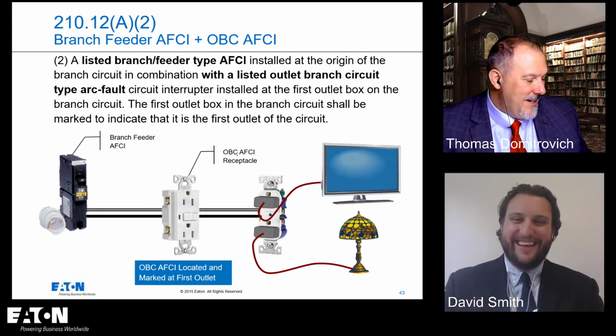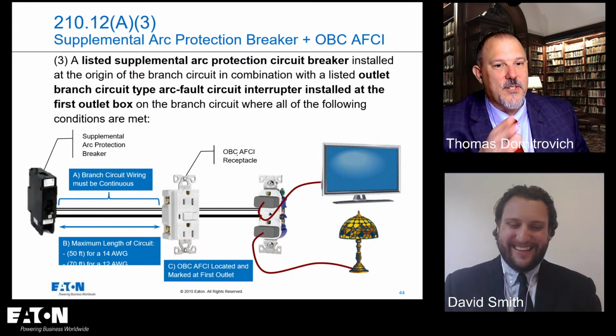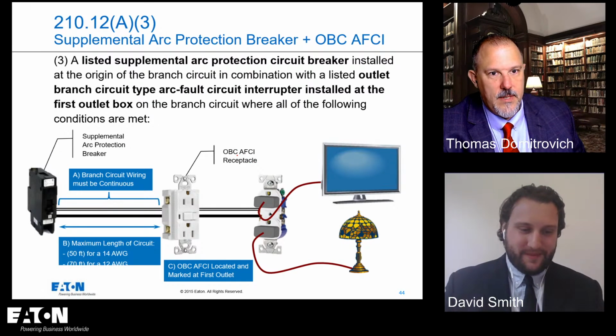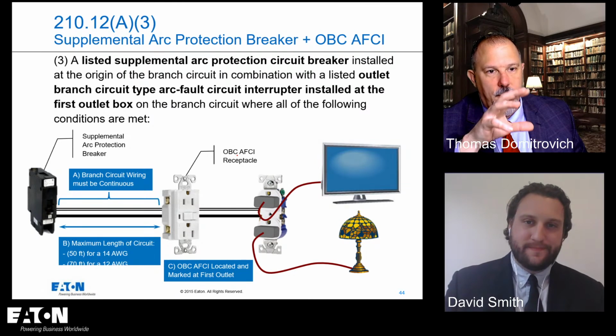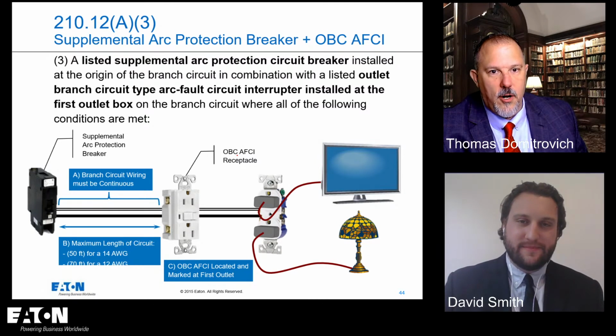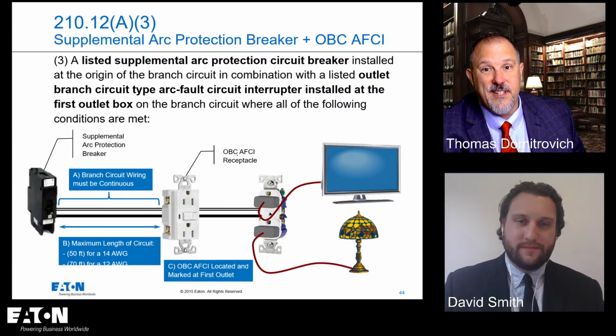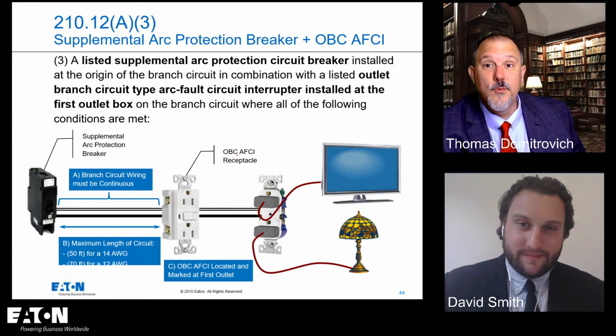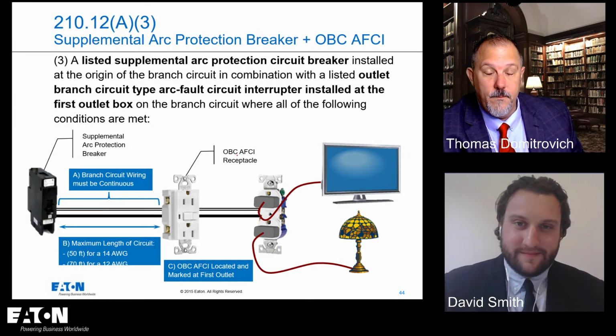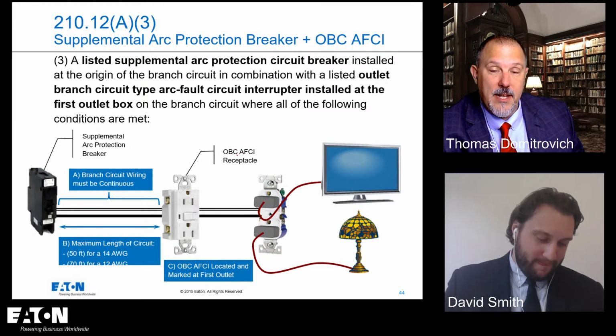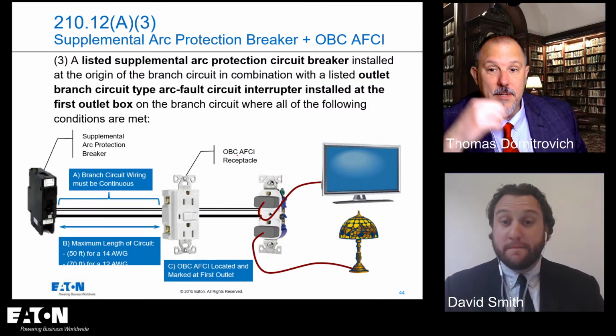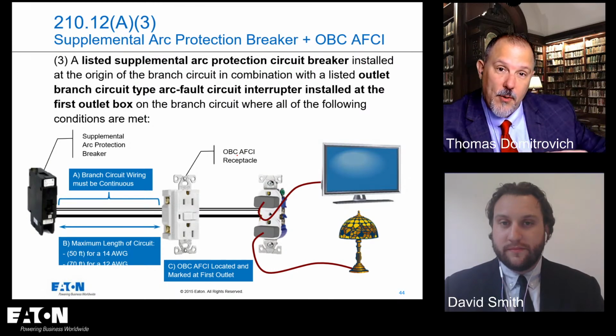Yeah, well, and understand too, this is where things are going to get deep. Okay, so the third option is a listed supplemental arc protection circuit breaker, and I'll tell you exactly how this came to be. I was in the room when they made the decision to put in 3 and 4, and it wasn't at the code panel meeting, it was a task group meeting that was in a separate room, and the task group, remember, code panels break out into task groups.